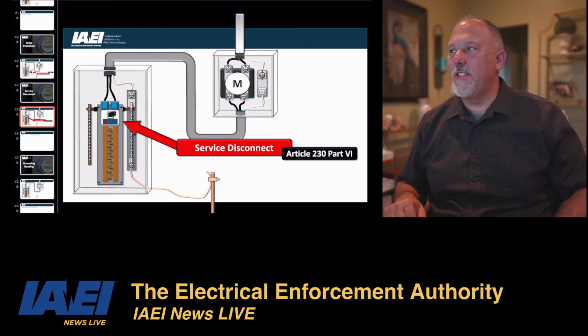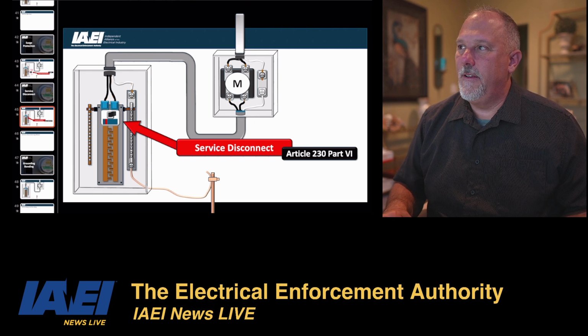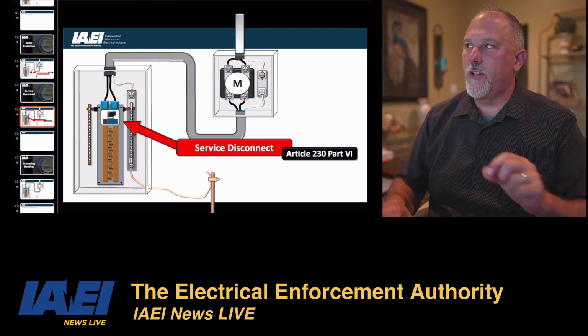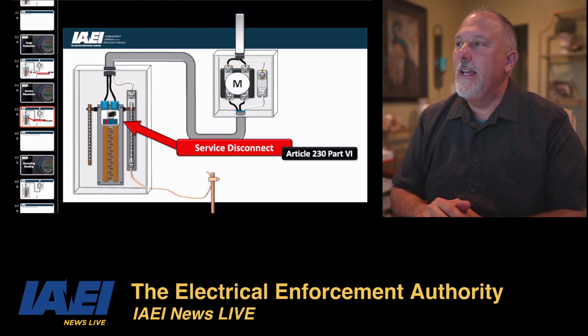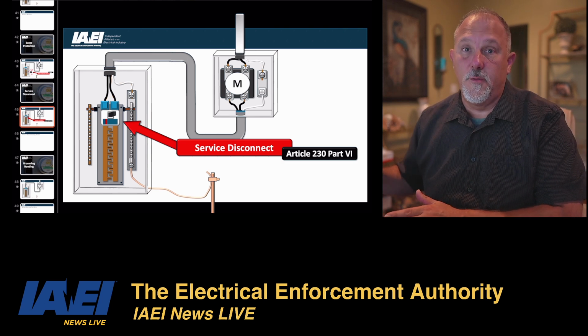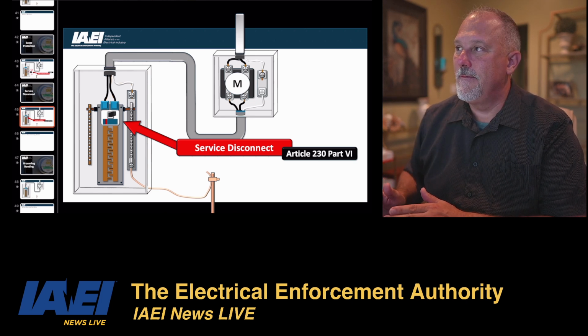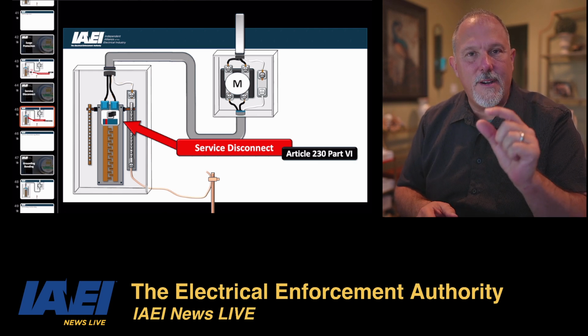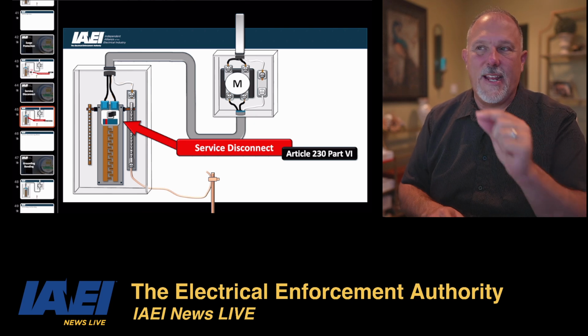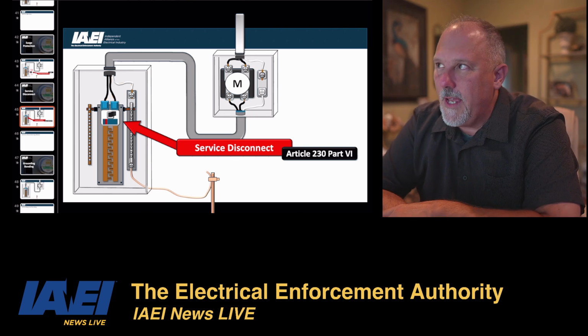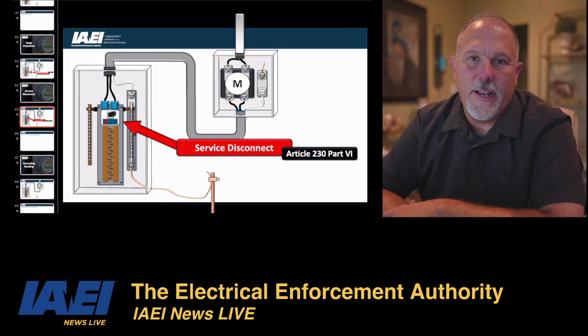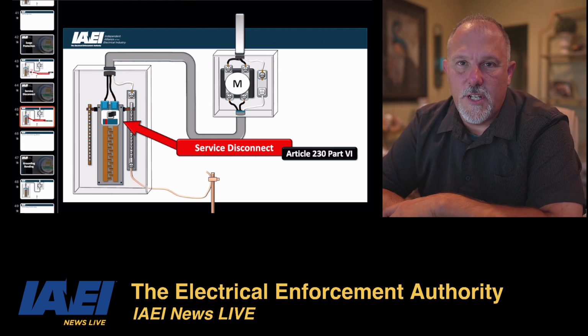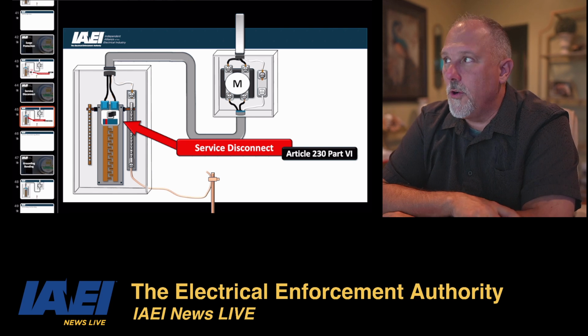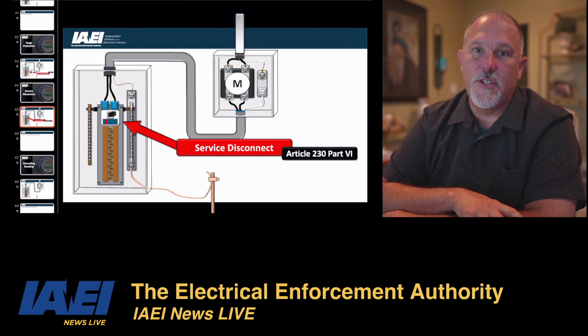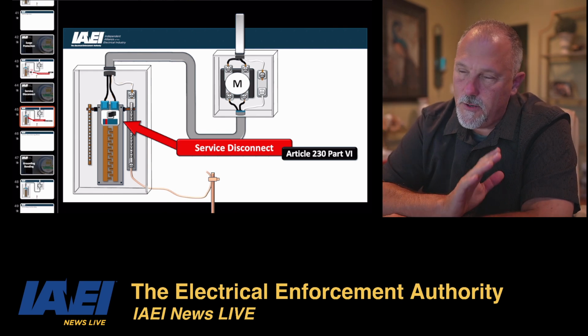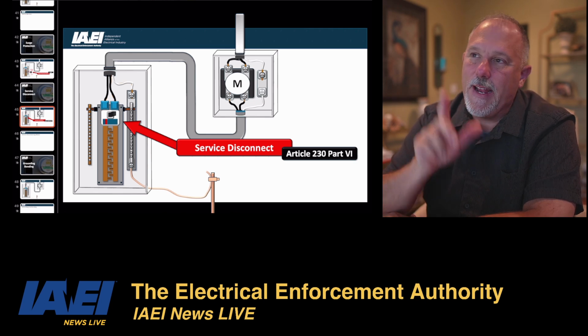It's not that it has to be marked as, it doesn't have to be marked suitable for use as service equipment. It has to be marked to identify that it is suitable for use as service equipment. So there's a very important little detail to understand in that language. So you can have service equipment 1,000 volts or less that is suitable for use only as service equipment and marked as such. Or you can buy it where it is suitable for use as service equipment, marked as such. So just be a little careful in that.